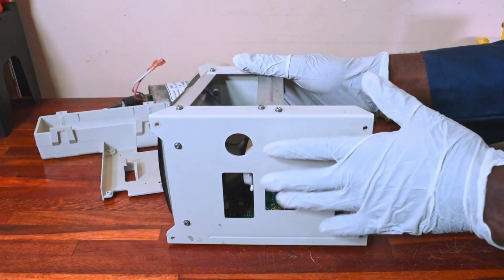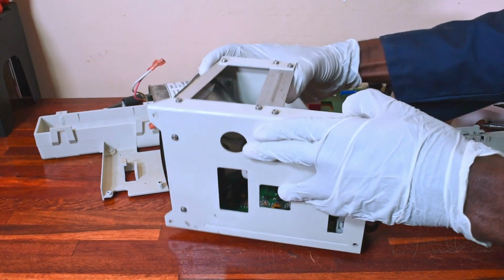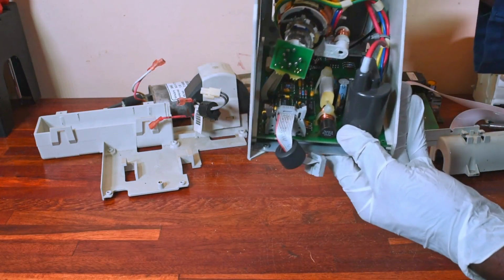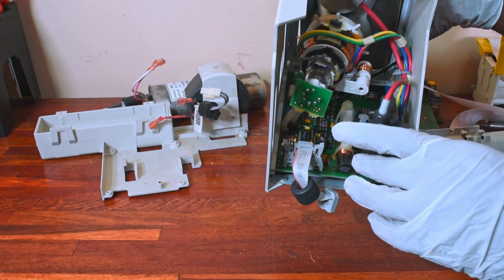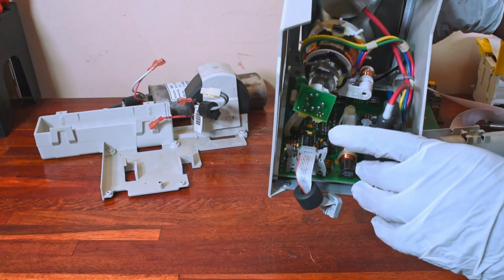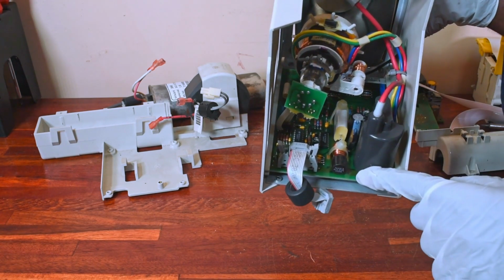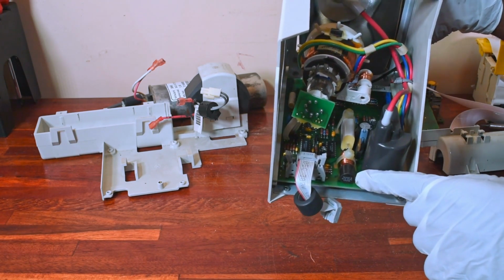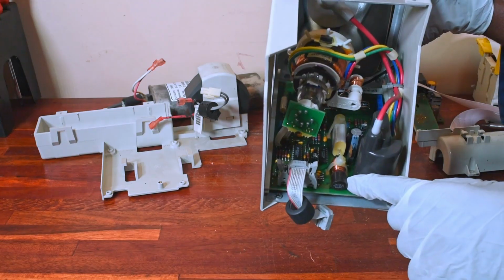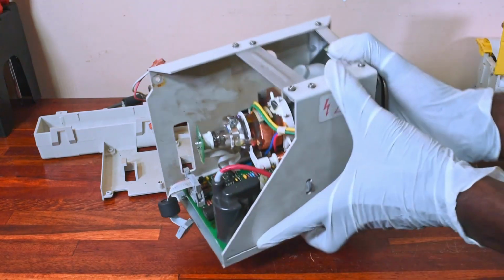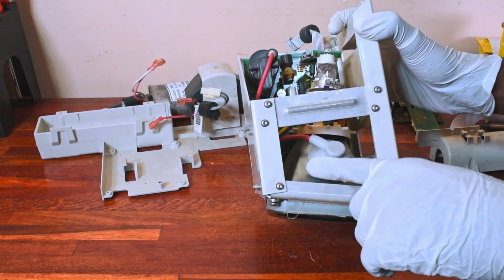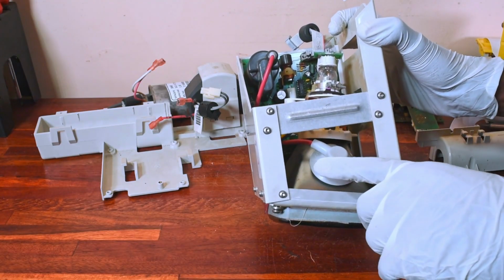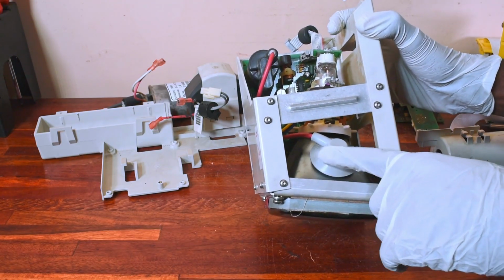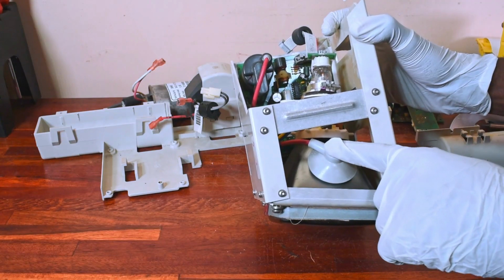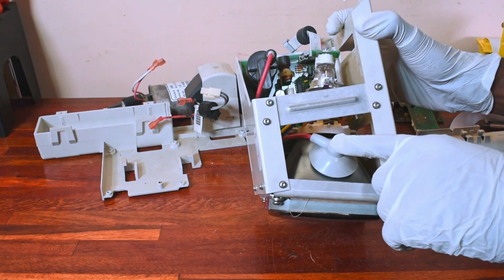Now, let us look at the CRT assembly. Located on the CRT assembly is the CRT deflection control board. This board drives the electron beam to generate and display real-time ECG waveforms. And over here is the CRT. The CRT can be removed by disconnecting the high voltage connection right here from the side of the CRT.